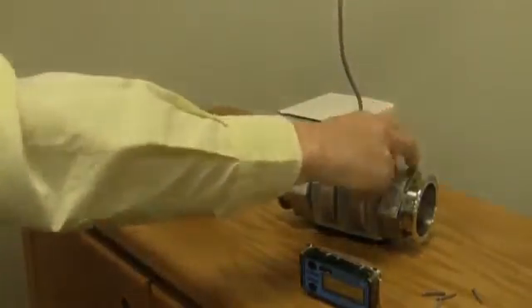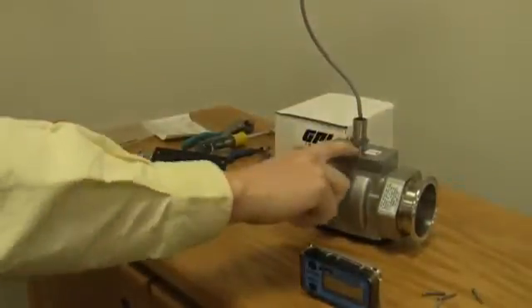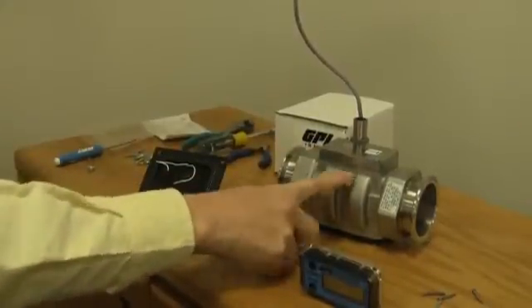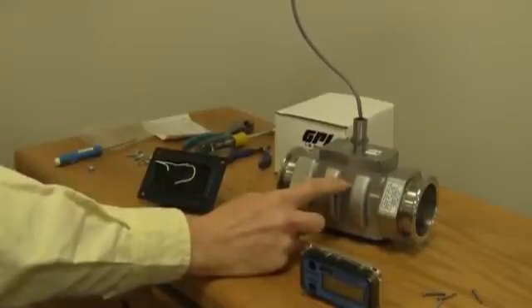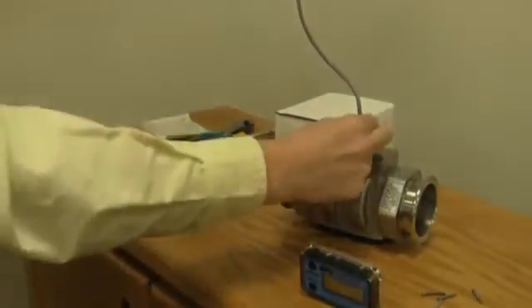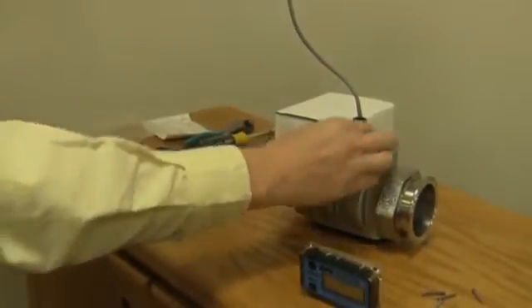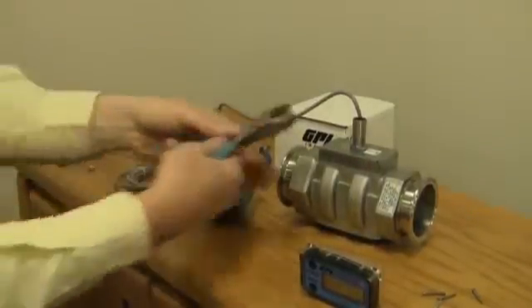One of my problems is sometimes I've had people have the nut hit and they think they've bottomed out on the turbine body as opposed to letting the actual magnetic pickup hit the turbine body. If it's too far away it won't pick up the turbine spinning. Now I've got that nice and snug, you don't need to use a wrench or anything. Put this jam nut down—now there I would use a set of pliers or something, just tighten it up a little bit.